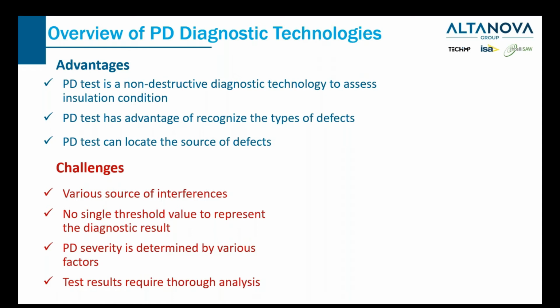So we talked about the advantages, and now the challenges, or what are the reasons stopping people from employing partial discharge, what's the reason stopping PD from getting so popular? There are some challenges that we need to handle when selecting or using partial discharge testing. First, we need to make sure that the signal we measure is partial discharge signals. And the problem of the field test is there is a lot of noise or interference on site. So the first problem is how can we ensure that the signal measured with a device is PD signal, or is the PD signal of interest.